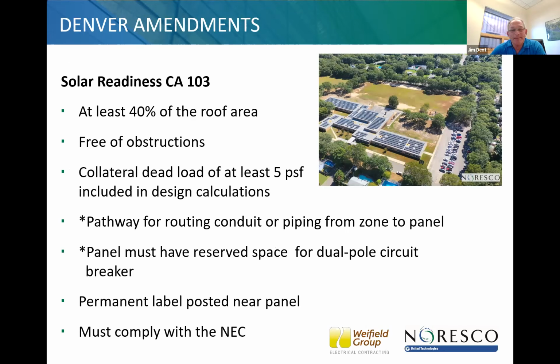So Denver's got solar readiness in as an appendix. It's appendix CA, and you see the two items that are asterisked here: the pathway for routing conduit or piping from the zone to the panel. You have to account for that in Denver for solar readiness. And the panel must have reserved space for a dual pole circuit breaker.